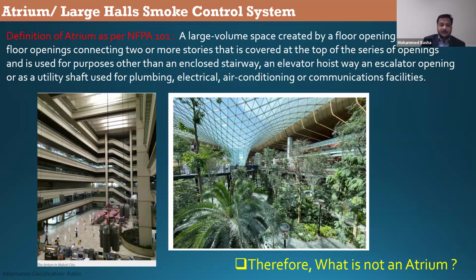So what is the definition of an atrium as per NFPA 101 or any other standard? This is the common definition: a large volume space created by a floor opening or series of openings connecting two or more stories, that is covered at the top of the series of openings, and is used for a purpose other than an enclosed stairway, hoistway or escalator opening, or a utility shaft for plumbing, electrical and air conditioning or communicating facilities. As I mentioned before, the openings are classified in different ways: communicating spaces, convenience openings, vertical openings, atriums.